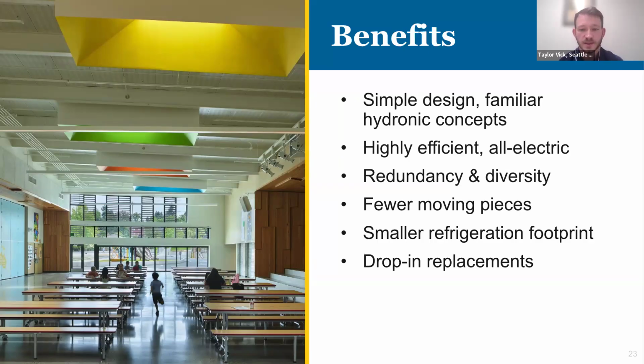The last point here: a lot of our newer buildings are all ground source heat pumps where they can be. But now we're moving some of our existing hydronic sites into these heat pump implementations. It's really easy to take an existing gas boiler and replace it with a couple heat pumps that serve the same purpose, so we can get clean energy benefits without a lot of work in the building. We see a lot of benefit going down the road for our existing sites.